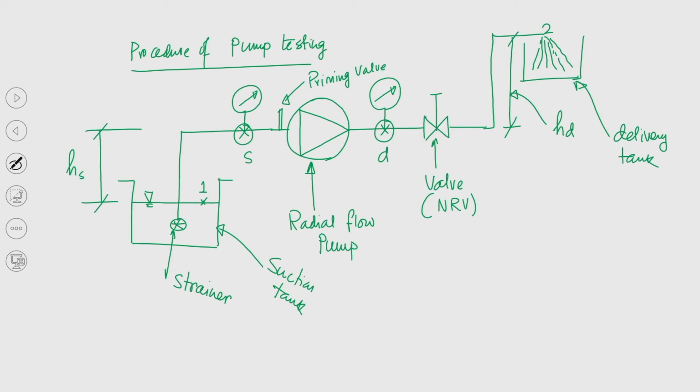Now, pressure will be built up, and eventually liquid will be transported to the delivery tank, right. So, that is what we have seen. In fact, you can understand that the total head that the pump should be able to develop will be able to overcome the static height Hd. On top of that, we also need a certain amount of velocity at this discharging point. That is nothing but the kinetic head, which we discussed in the last class when we talked about pump reaction.